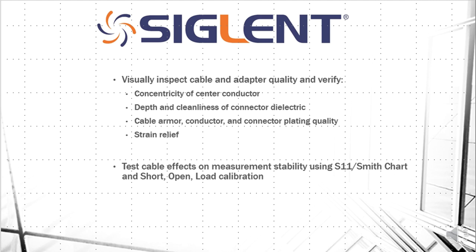I'd like to close by summarizing. We want to visually inspect the cable and adapter quality, and we want to verify the concentricity of the center conductor, the depth and cleanliness of the connector dielectric. We want to check the cable armor for any fraying and also a good feel. We want it to be linear. As we move the cable, we don't want kinks or anything like that. We want to look at that conductor and connector plating quality, see if there's anything flaking off. Then we want to take a look at that strain relief. Has it been overused? Is it starting to break down? That's going to indicate that the dielectric inside and the shielding inside may also be frayed.